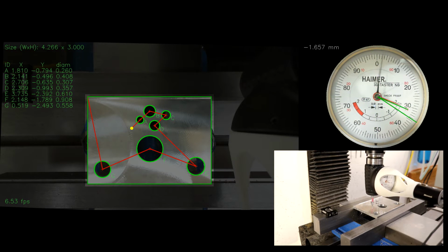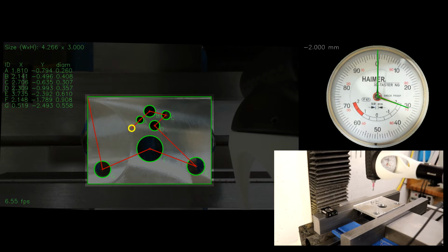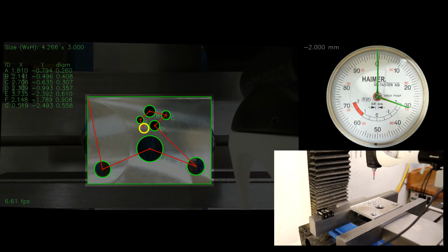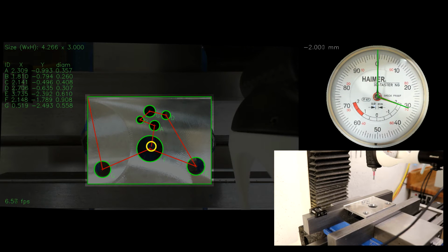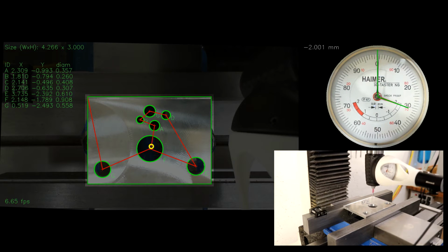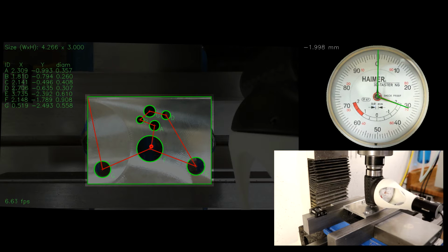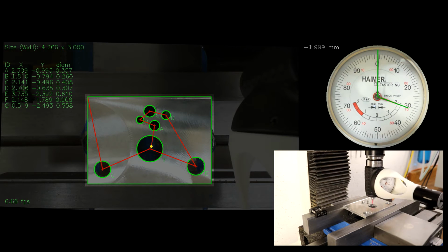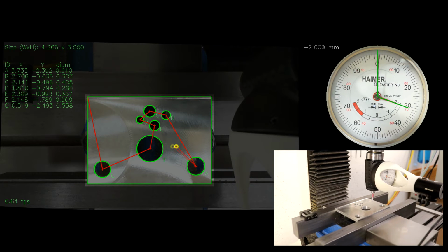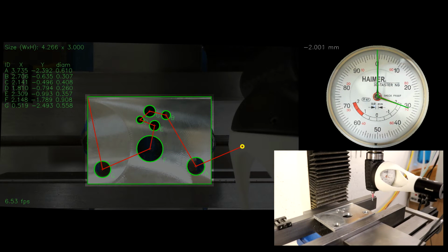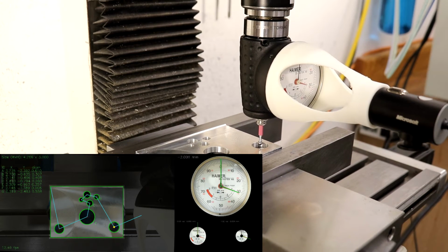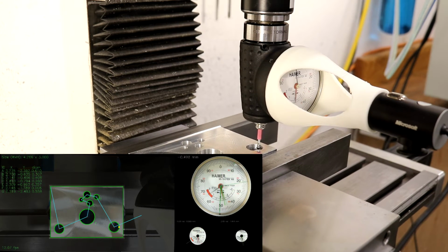The software integrates the augmented views from both cameras, with the Haimer 3D sensor probe tip shown as a yellow or red circle. The circle is red if the probe tip is below the z equals 0 plane, otherwise it's yellow, and the diameter indicates relative z height. Once ready, the probing path is locked, indicated by change in color. Locking the probing path removes a lot of calculations and allows the frame rate to increase, and a high frame rate is necessary for catching unexpected probing events.